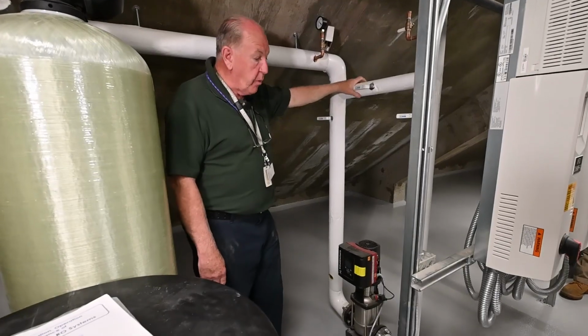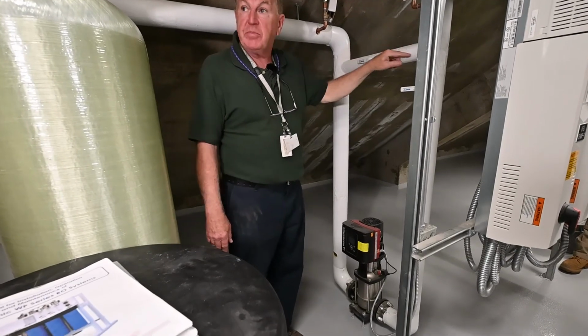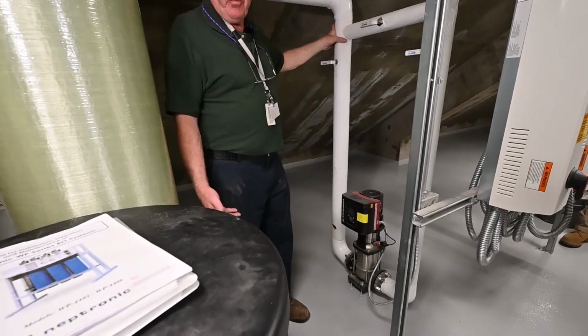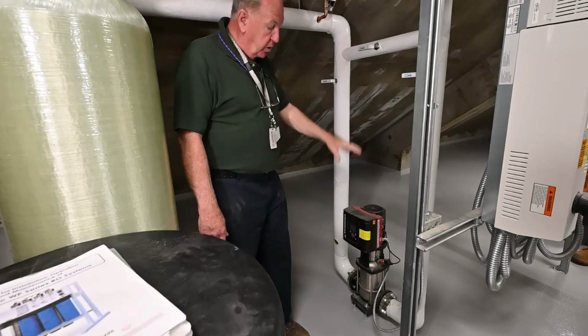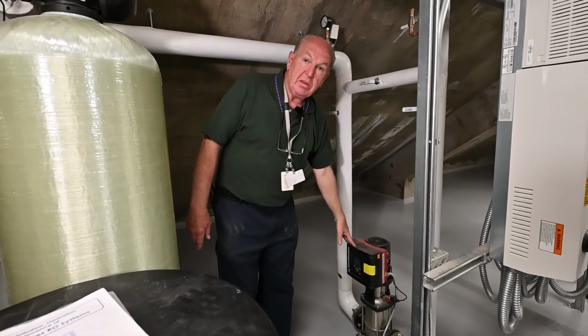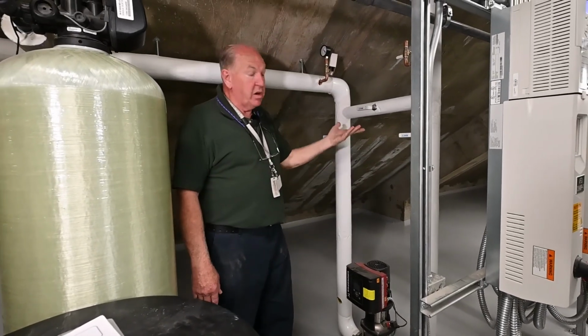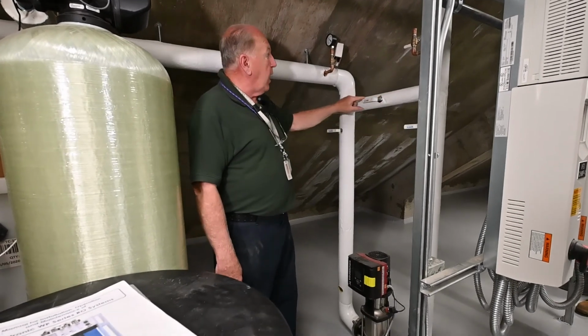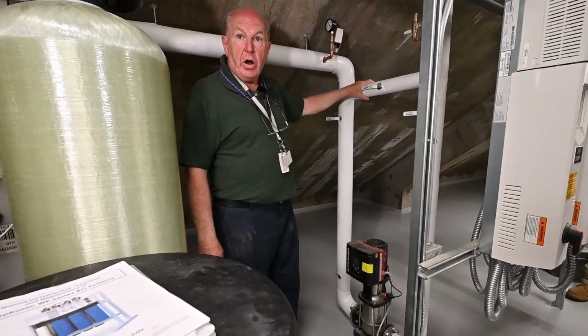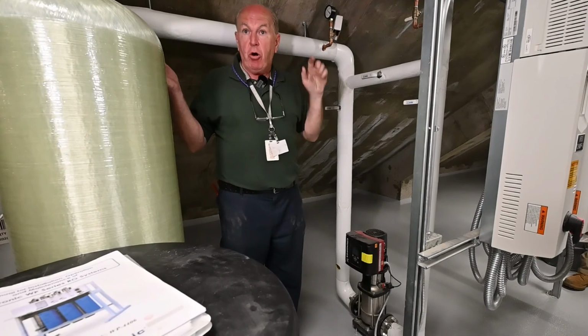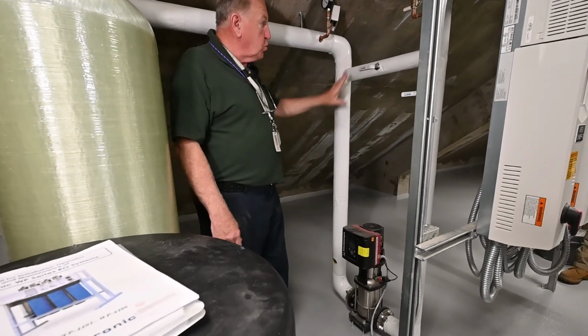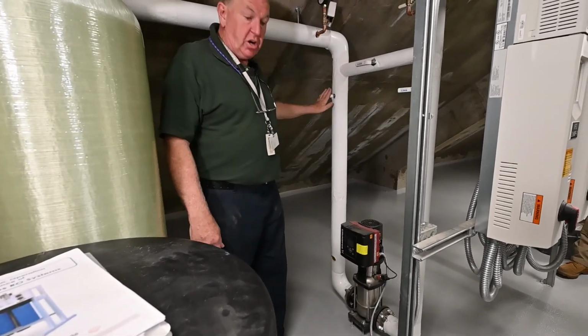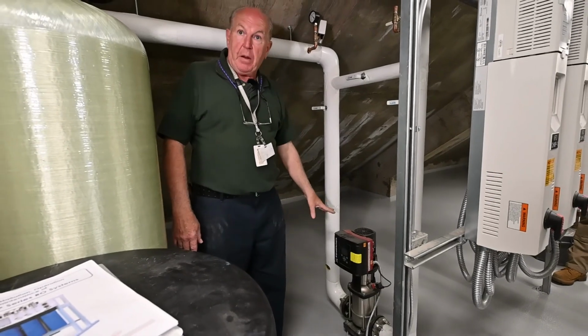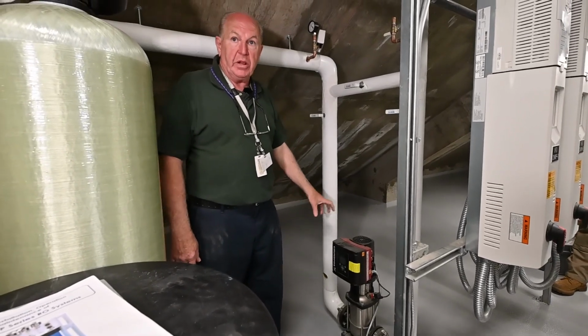The design called for a pressure booster on the city water coming up to the. They didn't think they'd have enough pressure up here, so they put a pressure booster pump in. That's not really necessary because this building has plenty of water pressure. So we opened the bypass, and it works on the regular city water pressure. It's sufficient for the RO system supply. That's why this bypass is open and these valves are shut. But this pump is there in case there wasn't enough building water pressure.